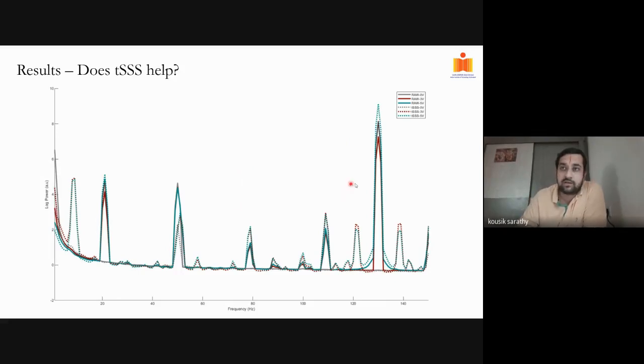And it is interesting. Some things we would immediately recognize: power line noise. This is something we anyway know will happen. And then there is the DBS artifact. The stimulation was at 130 hertz, so we have a nice DBS artifact peak. We also found an interference peak somewhere around 80 hertz, possibly the destructive interference between power line 50 hertz and the 130 hertz.